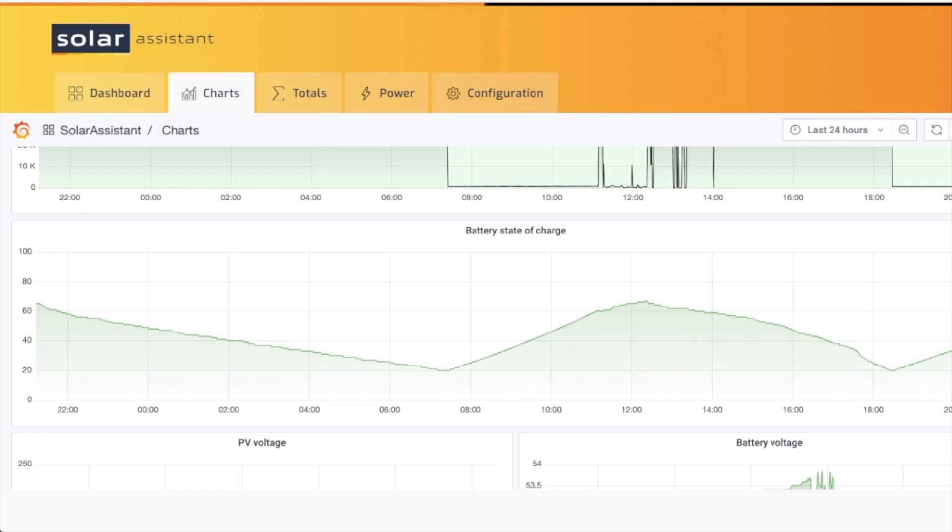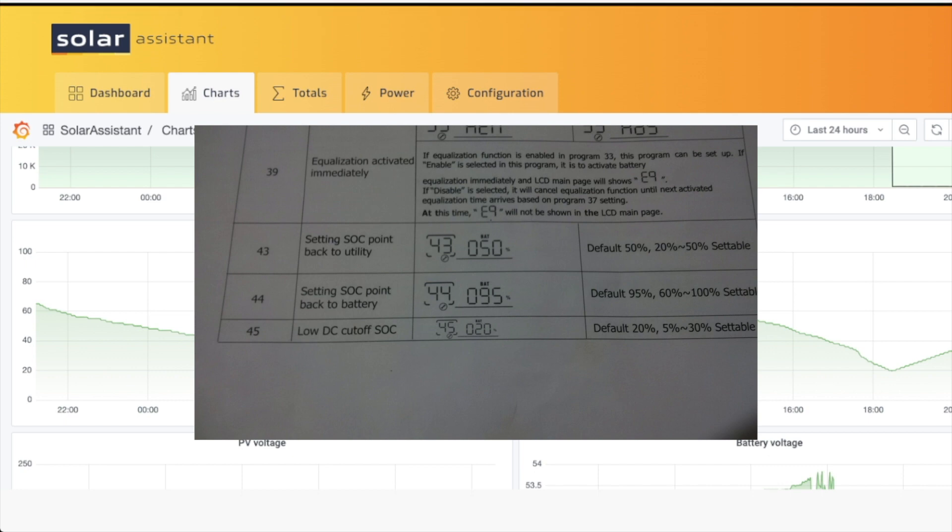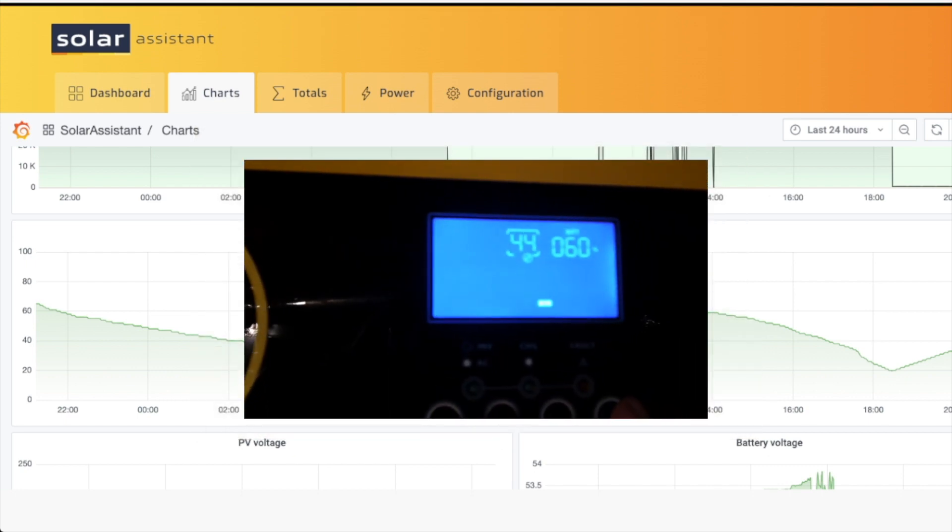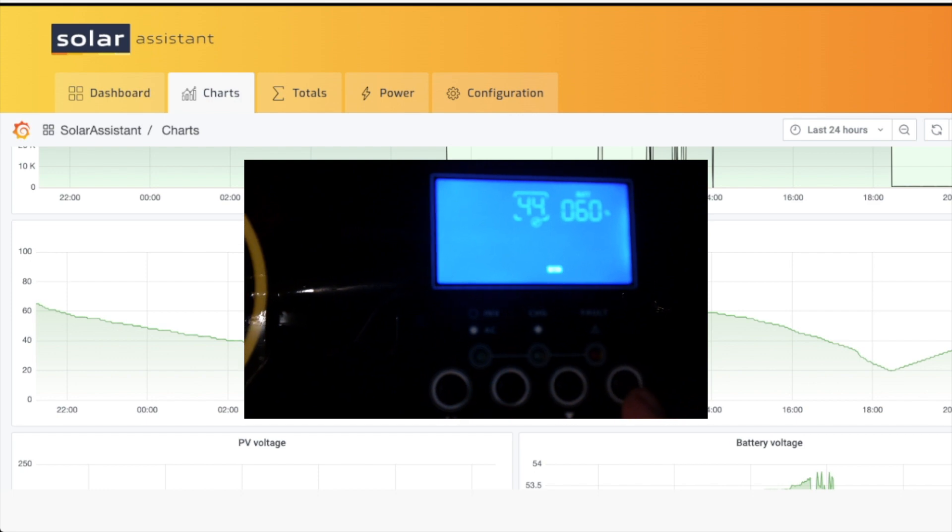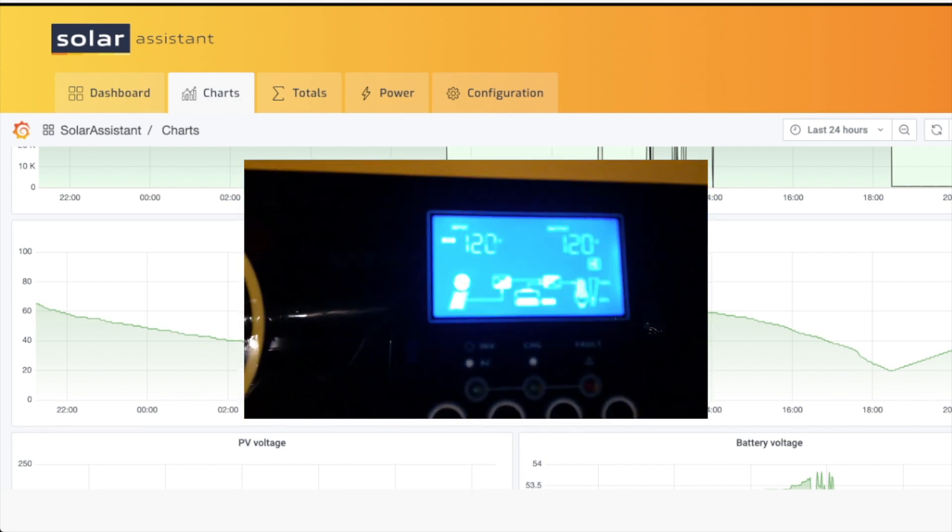Now likewise, for option 44 in the menu setting, the state of charge point back to battery, I set that again as low as possible. So I have mine set to 60, which I think is the lowest you can set it to.